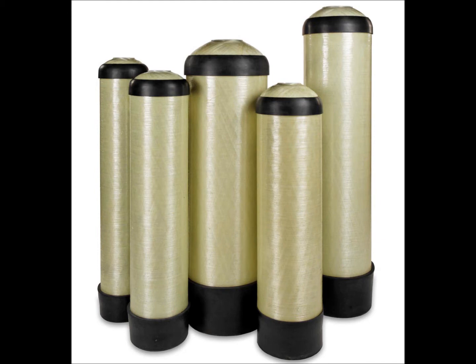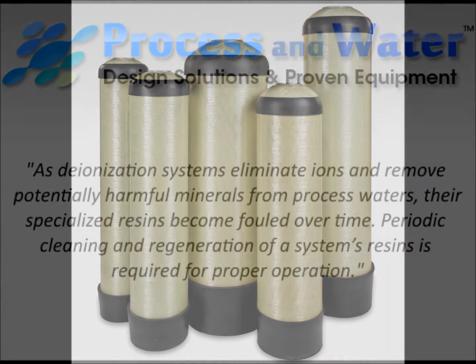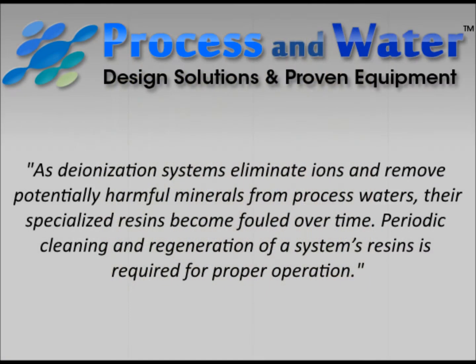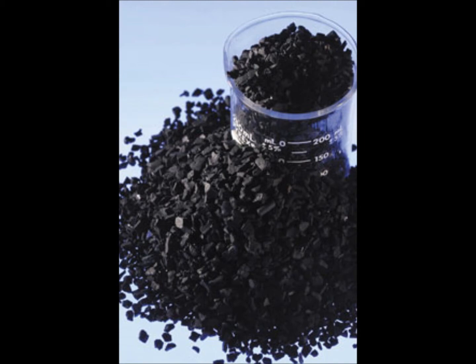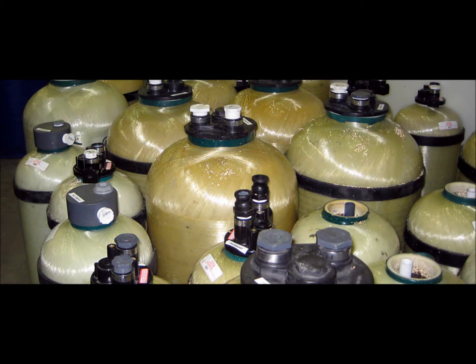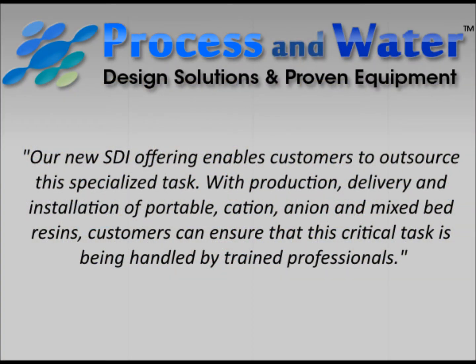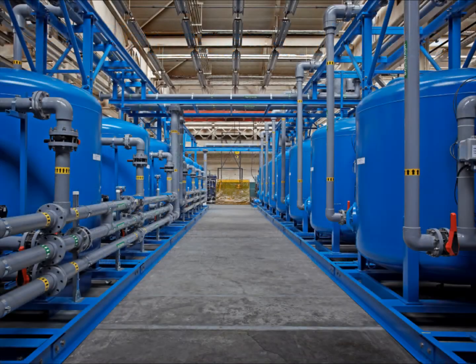As deionization systems eliminate ions and remove potentially harmful minerals from processed waters, their specialized resins become fouled over time. A periodic cleaning and regeneration of a system's resins is required for proper operation. Resin regeneration is a complicated process that involves precision handling of a variety of chemicals, often toxic and dangerous ones.